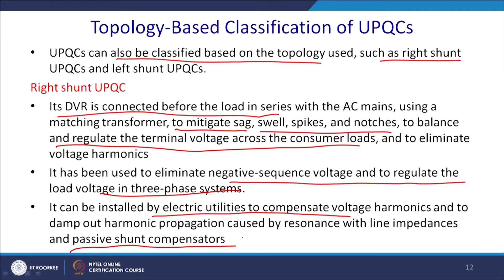to balance and regulate the terminal voltage across the consumer load and to eliminate voltage harmonics. So, whatever the power quality issue related to the voltage, it is cleaned up by the DVR. It has been used to eliminate the negative sequence voltage and to regulate the load voltage of the 3-phase system. Moreover, it can be installed by the electric utilities to compensate the voltage harmonic, to damp out the harmonic propagation caused by resonance with the line impedance and the passive shunt compensator.